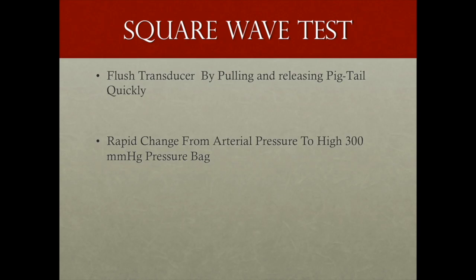This will result in a rapid change in arterial pressure from whatever the patient's inherent arterial pressure is to the pressure that is in the pressure bag, which should be kept at 300 millimeters of mercury.